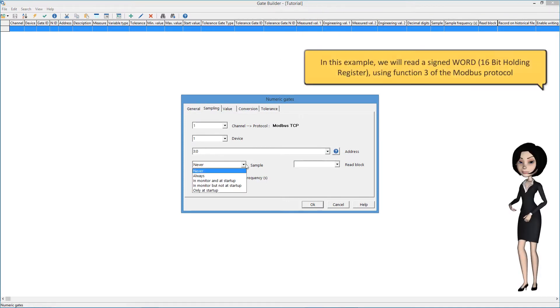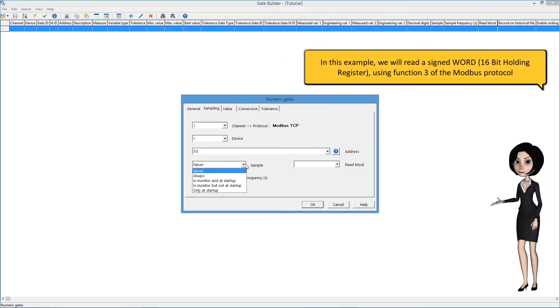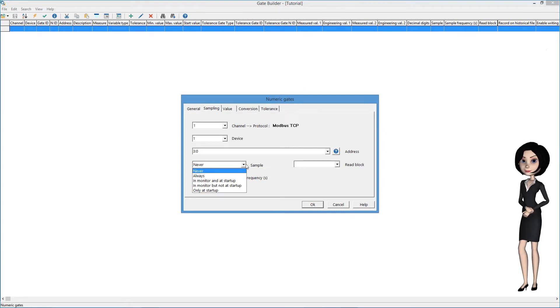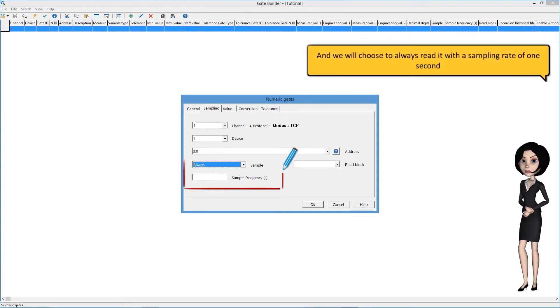In this example, we will read a signed word — a 16-bit holding register — using function 3 of the Modbus protocol. And we will choose to always read it with a sampling rate of 1 second.